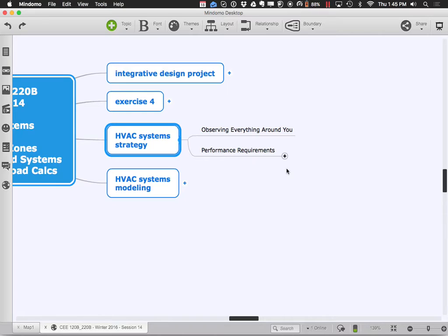I'd love you to start observing everywhere you go and try to figure out how the HVAC system is working. In this building — the Y2E2 — the HVAC system is largely hidden. Under all these floors there are radiant tubes that either heat or cool the concrete floor to a base level close to anticipated load. At night, vents at the top of the skylights open along with outside windows for 'the big flush,' where hot air rises and gets sucked out of the building, cooling everything down.